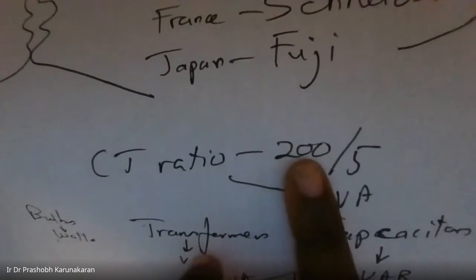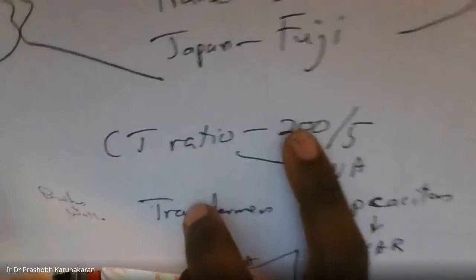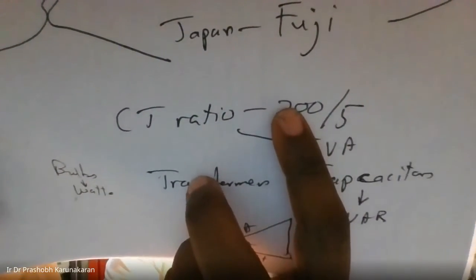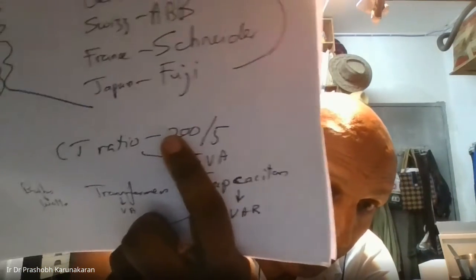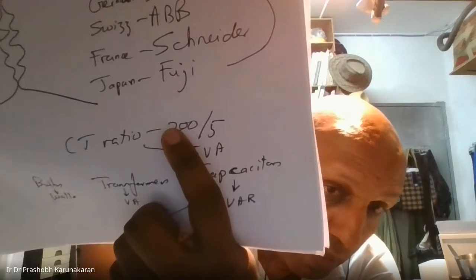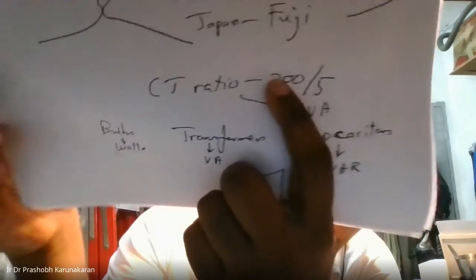So what you do in the injection test: if your CT ratio is 200/5, you put in 200 and make sure it doesn't trip. If it trips, something is wrong, because it's not supposed to trip at 200. At 200 plus 5%, it should trip. Let me show you.